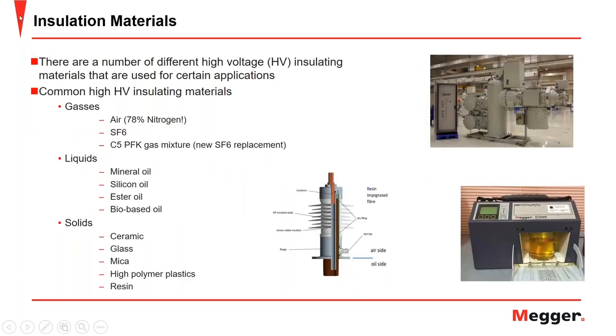So when we talk about insulation materials, there are a number of different high voltage insulating materials that can be used for certain applications. Here we have a list of common high voltage insulating materials, starting with gases. That can range anywhere from air, which is 78% nitrogen, and that's very important when we talk about partial discharge, and we'll discuss this importance a little bit later. This also includes SF6, C5-PFK gas mixture, and it includes liquids such as mineral oil, silicon oil, ester-based oil, and bio-based oil, and then ultimately solids such as ceramic, glass, mica, high polymer plastics, and resins. The takeaway from this is that each material has its own permittivity and dielectric strength, making some of these materials more susceptible to PD activity, as well as the different properties of these materials causing different characteristics of partial discharge themselves.